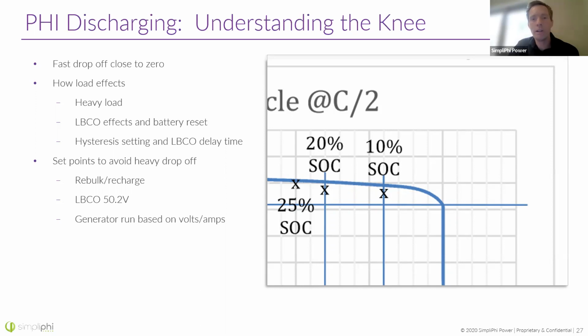Additionally, heavy load at low states of charge is another added burden on the battery. It's really hard on the battery to have a heavy load when you're at a very low state of charge. There's a physical reason for this, having to do with the density of charge carriers within the cell, meaning the lithium ions. When a battery is 95% discharged, you have very few charge carriers left to carry the current. So if you're demanding a large amount of current, those charge carriers have to move that much faster, which is much harder on the battery. You get a lot more heat production at low states of charge when discharging at heavy loads. So keep that in mind.